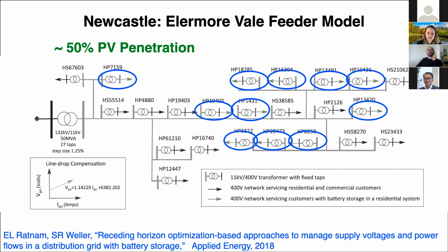This model goes from the zone substation, the 132 to 11 kV transformer, all the way through the distribution feeder to what we call the distributors, from the 11 kV to 415 transformer to the customer's home, which is the distributor there.